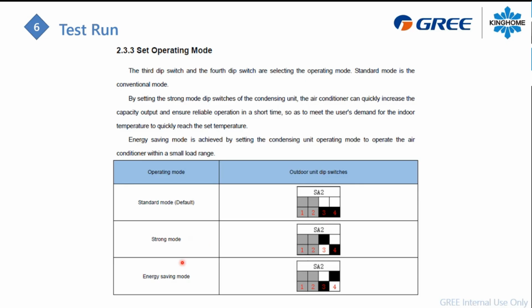Or you can go the other way and select energy saving mode by flipping dip switch number 4 to on. The compressor will then stay at a low capacity for a longer time. For example, you set up a 3-ton unit and the ductwork is designed for a 3-ton unit. You adjust the CFM, the airflow, everything, but you still don't remove enough humidity from the air because it's too fast. In cooling mode the unit operates only 15 minutes and it's done. It's cold, but it's still humid in the house.